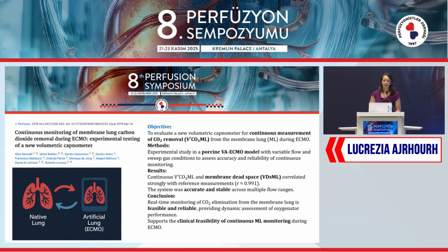This experimental study evaluated a novel volumetric capnometer device to enable continuous monitoring of CO2 removal by the membrane lung during ECMO support. Researchers conducted the work in an animal porcine VA ECMO model with varying blood flow to sweep gas ratio. The capnometer measures VCO2 and membrane dead space. And these parameters, the VD, the VD ML, demonstrated high accuracy and strong correlation with the standard measurement technique across multiple flow conditions.